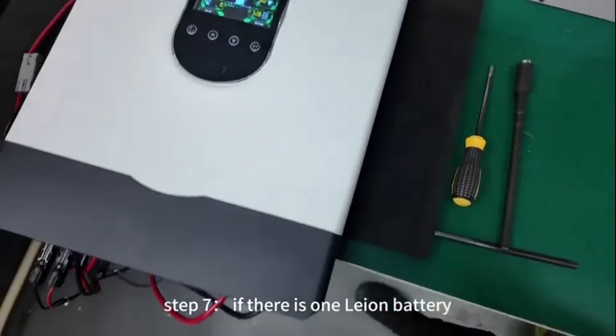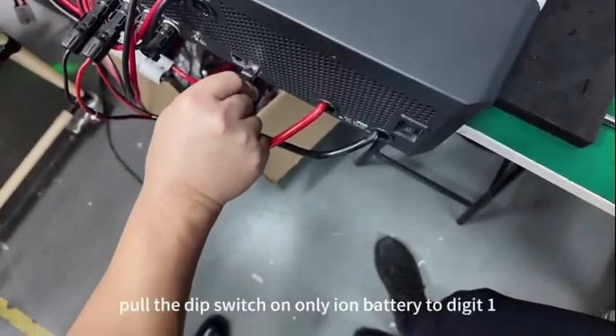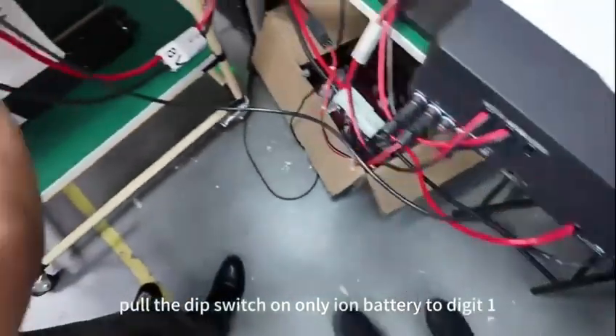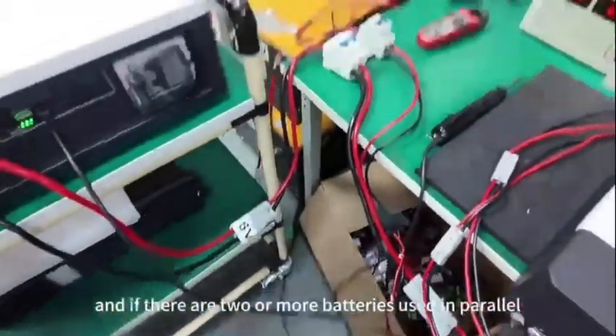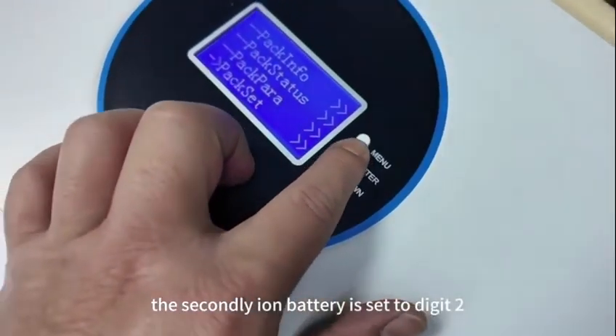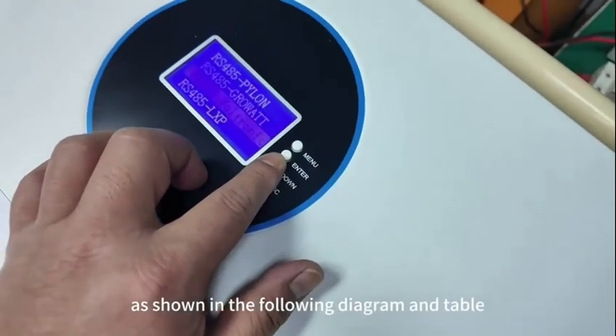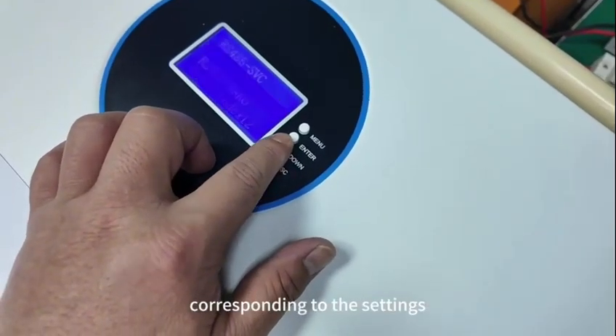Step 7. If there is one Li-ion battery, pull the dip switch on the Li-ion battery to digit 1. And if there are 2 or more batteries used in parallel, the second Li-ion battery is set to digit 2, as shown in the following diagram and table corresponding to the settings.